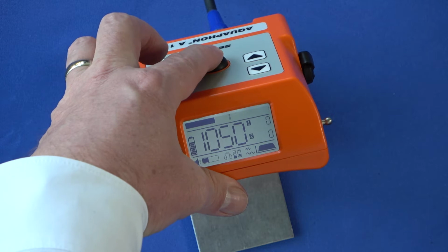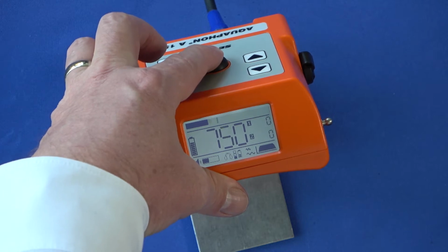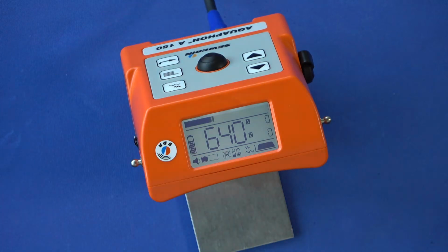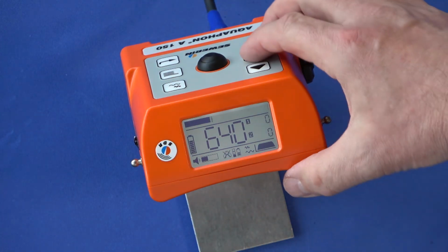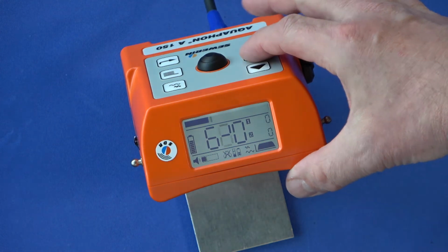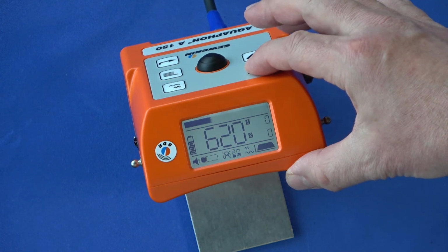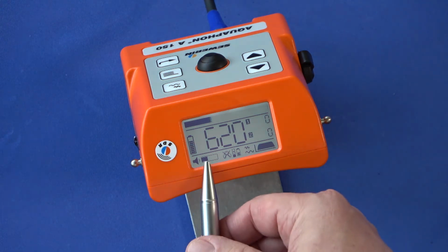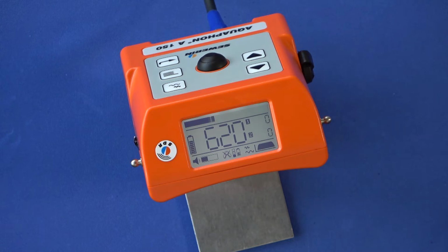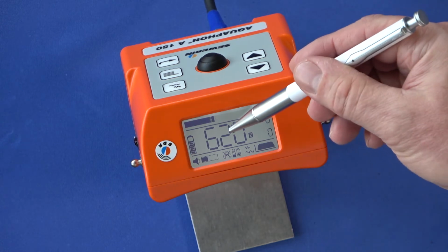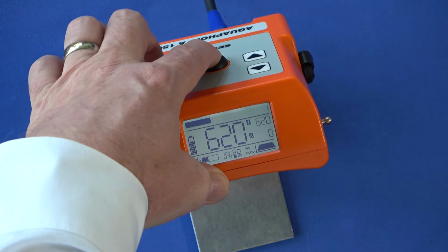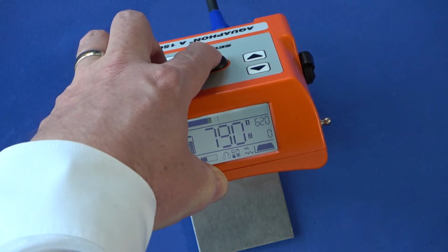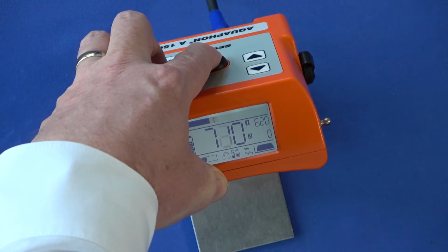On the headphone you can hear now in real time the sound that the microphone picks up. If necessary, adjust the volume using the arrow keys. The volume setting is shown in the lower left corner of the display. In the center of the screen you can see the measured minimum noise level. The measurement starts at 1999 and it is reduced until the minimum noise level is reached.